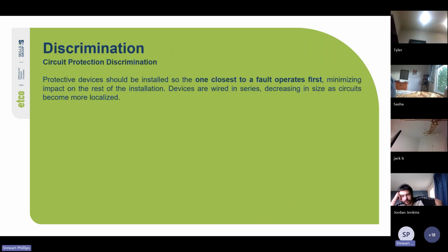Cool. So, discrimination. No, we're not talking about discriminating against Indigenous people. We're talking about the discrimination of protective devices. When we're talking about this, we're talking about installing them so that the one closest to a fault operates first, minimizing impact on the rest of the installation. So devices are wired in series, decreasing in size as circuits become more localized.